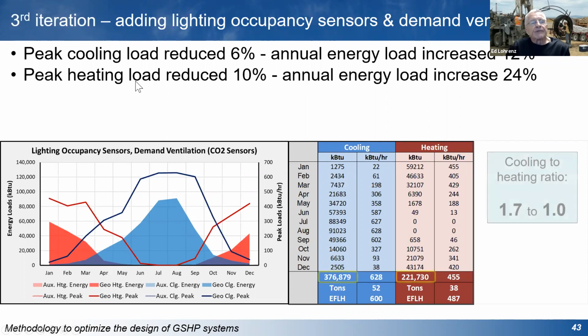Running a third iteration, using occupancy sensors to provide lighting only when it's needed. So meeting rooms that aren't occupied, we can shut the lights off, reduce the internal gains on the building, and provide fresh air based on CO2 sensors, providing fresh air only when it's needed. We've reduced the cooling load by reducing the lighting load, and reduced the heating load by reducing ventilation loads. So now we've reduced this energy balance from 2.3 down to about 1.7 to 1.